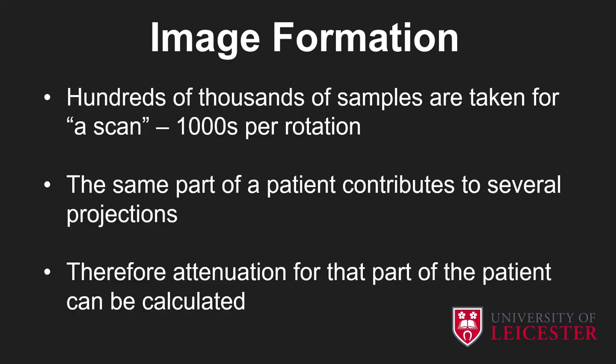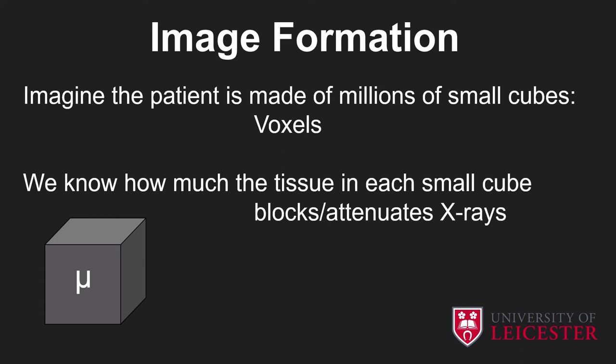In terms of forming the image, hundreds of thousands of samples are taken for a scan — thousands per rotation — and the same part of a patient contributes to several projections. All modern scanners scan the patient in a single continuous movement; the patient is driven through the scanner on the couch. It's no longer right to talk about a scanner requiring a slice at a time — the whole patient is scanned and those slices are produced later via the computer. Imagine the patient is made up of millions of tiny cubes — we call these voxels or volume elements — and by using all those projections, we know how much the tissue in each small box attenuates x-rays.